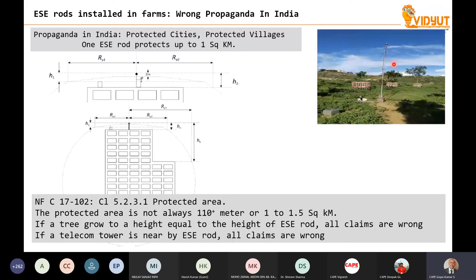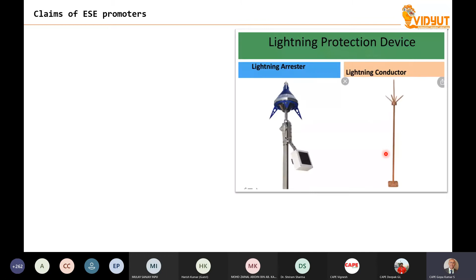This particular NFC clause explains about the protected area. The protected area is not always something plus or minus 100 meters. But the proponents, the supporters, say each rod can protect up to 1.1 to 1.5 square kilometers, and you must understand that even in the documents of the ESE standard, these are not correct. Then again, what do the supporters say?